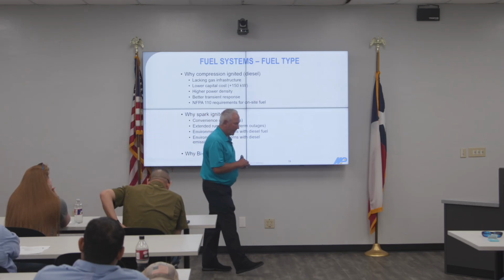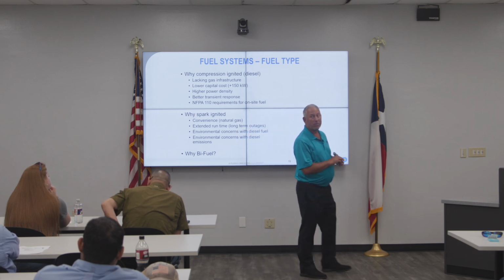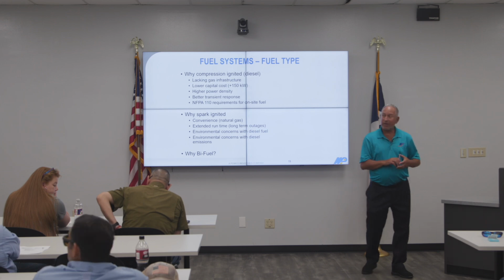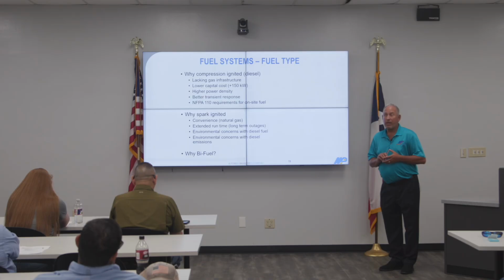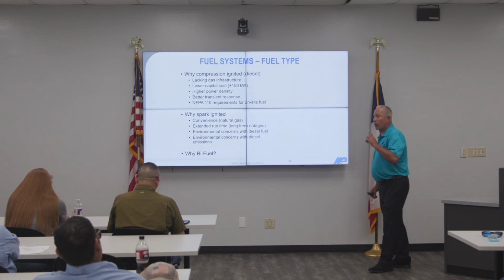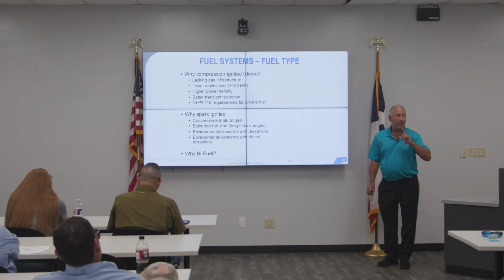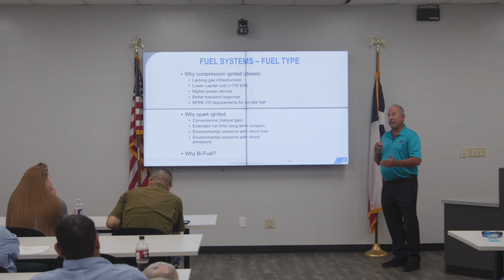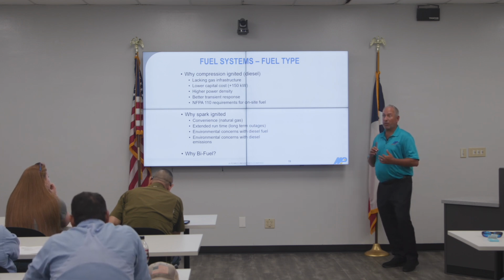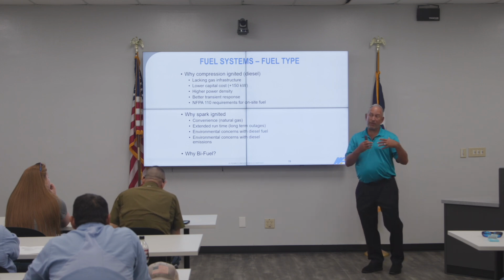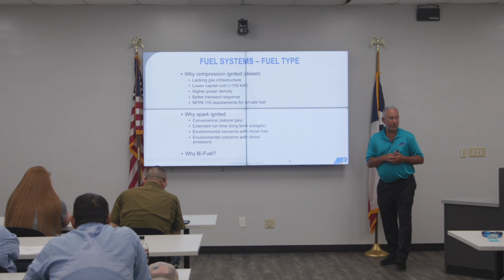What we've seen over the years is that natural gas has outperformed diesel delivery — it's been there. So we're seeing more authorities having jurisdiction, AHJs or fire marshals, accepting natural gas as a reliable fuel supply. The only exception is the code states that a level 1 hospital, with trauma and operating rooms, must have on-site fuel. They got very specific on that. So a bi-fuel is a good approach — it lets someone get into the natural gas world and use its benefits, but still meet code by having fuel at the facility.